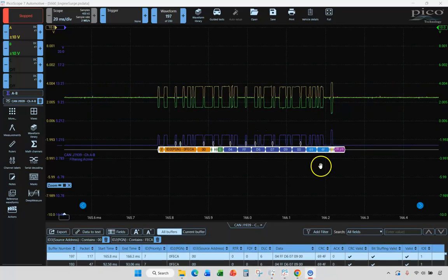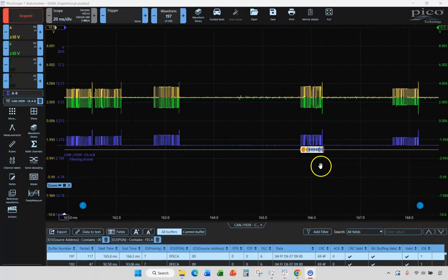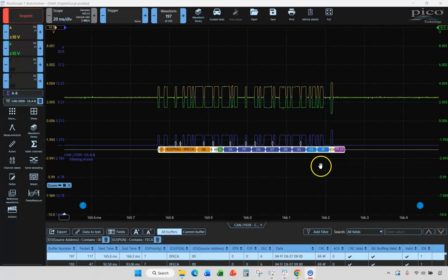Because of all the garbage that it's putting on the CAN bus, causing the CAN bus to be full of errors, source address 6 is not able to get a message to the engine controller within that 100 or so millisecond time period, and we end up with an active diagnostic trouble code in the engine controller indicating it cannot communicate with the cab controller, source address 6.